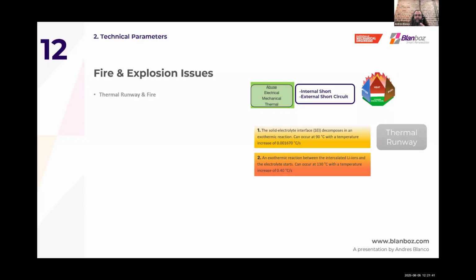Then an exothermic reaction between the intercalated lithium ions and the electrolyte starts, occurring at around 130 degrees with a temperature increase of about 0.40 degrees Celsius per second. Finally, an exothermic reaction between the positive material and the electrolyte takes place - the cathode starts short circuiting with the electrolyte, and also short circuits with the anode, so it's total chaos. This can occur at temperatures above 200 degrees, with a temperature increase of anywhere between 1.7 and 17 degrees Celsius per second. As you can see, the fire temperature increases very rapidly, which is why chemical fires, particularly in batteries, tend to be quite aggressive.